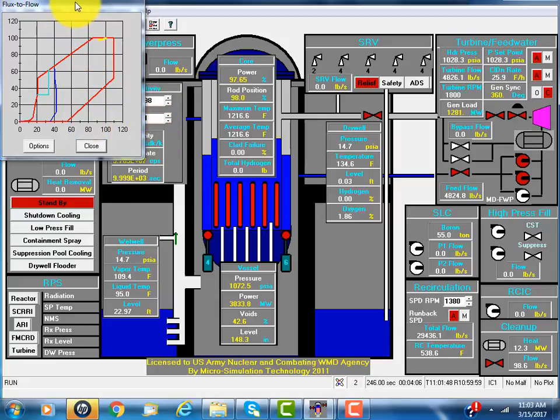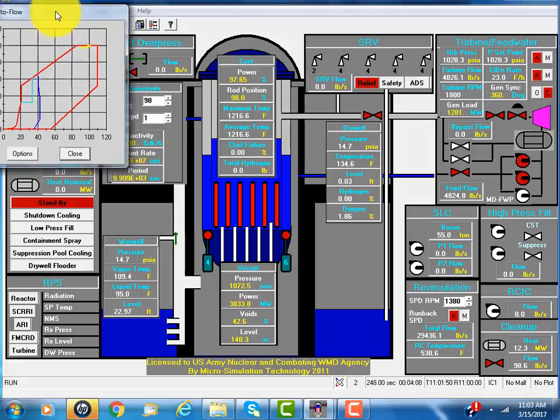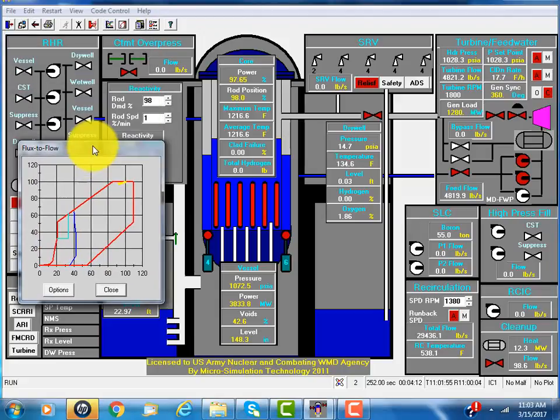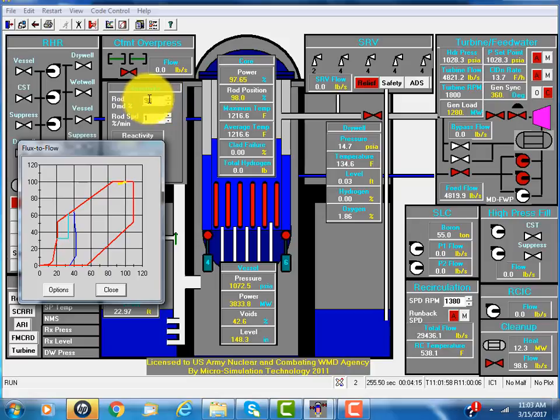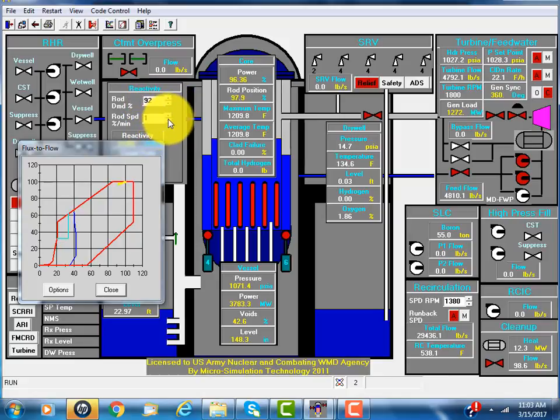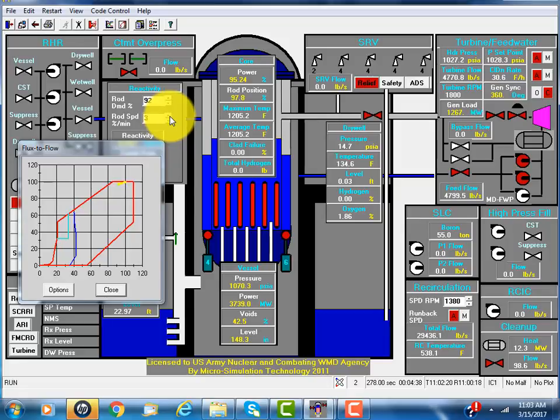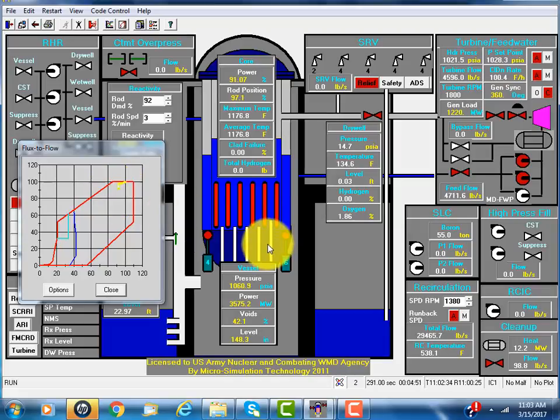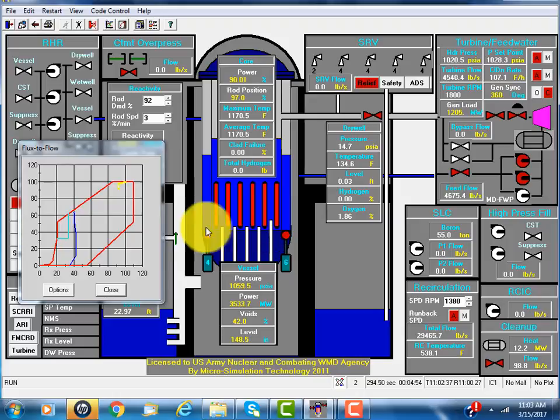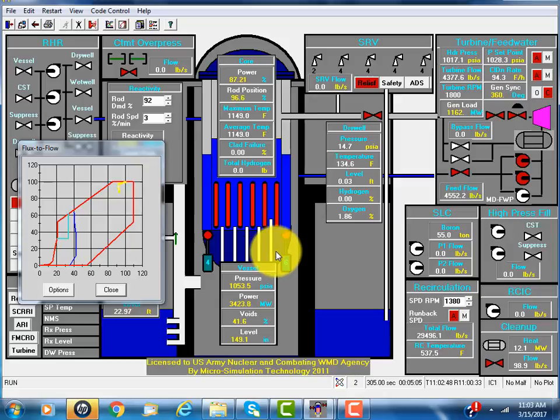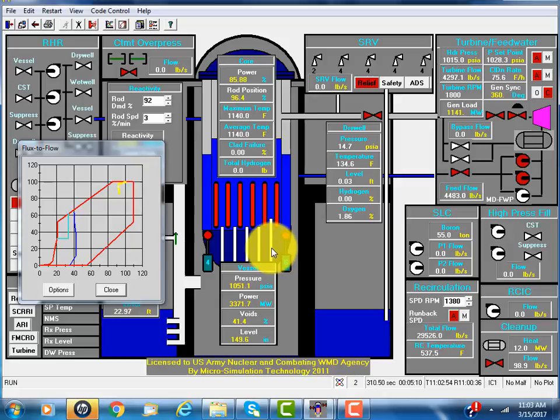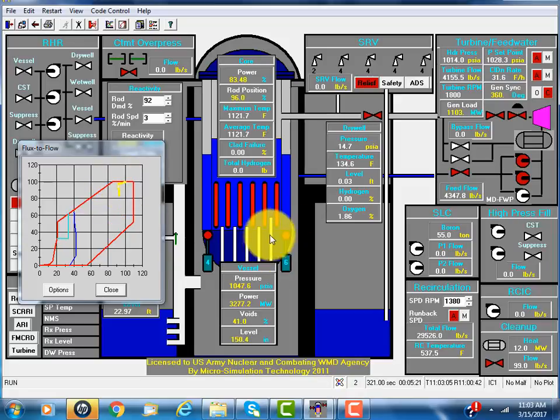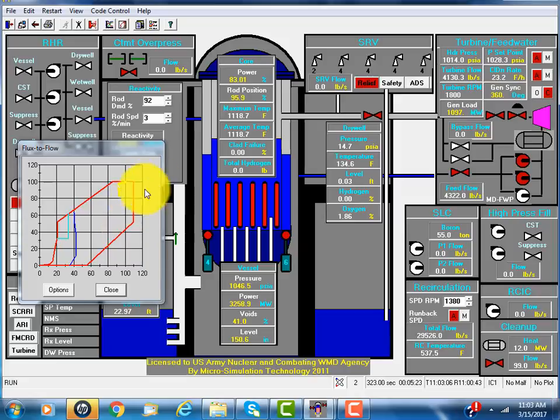That's not the only way to reduce power. We can also insert the rods. Right now it's 98% withdrawn. If we change it to 92% and make the rod speed a little faster, you see the power will drop as the rods go in. The rods have a strong neutron absorption material, such as boron. It absorbs more neutrons and power goes down.